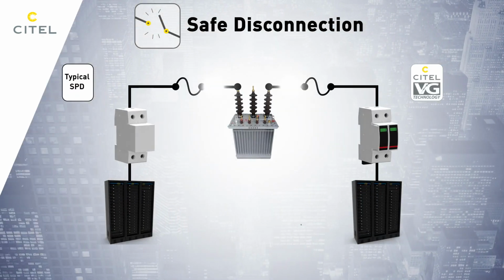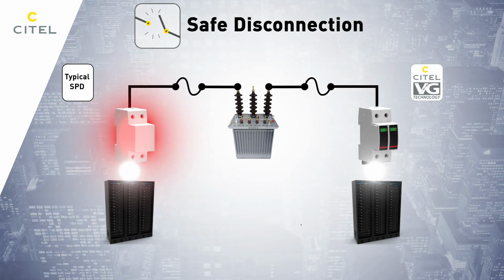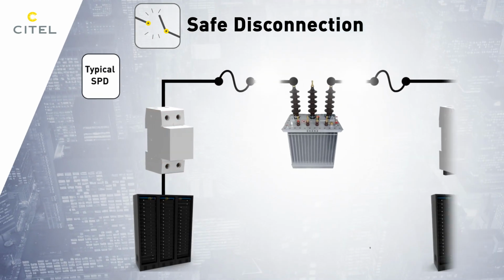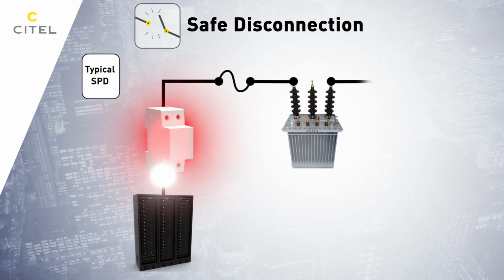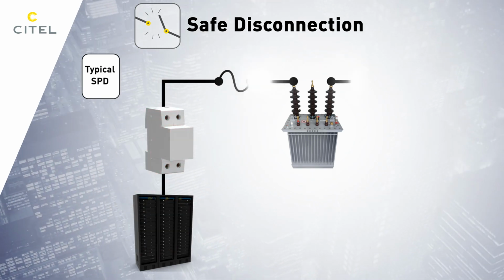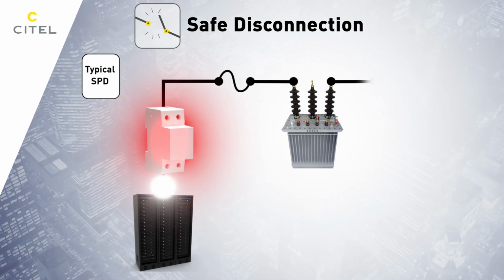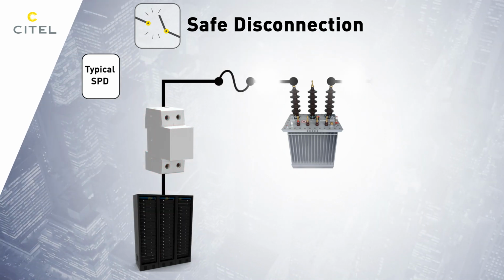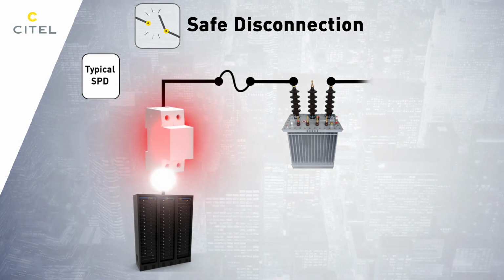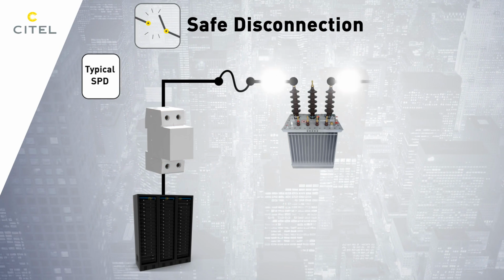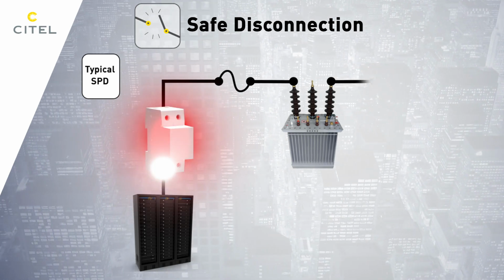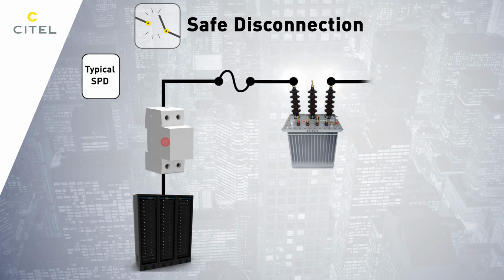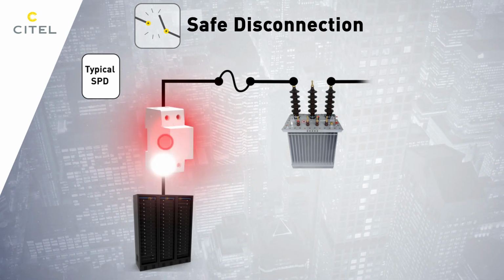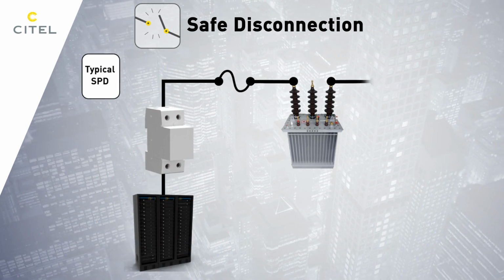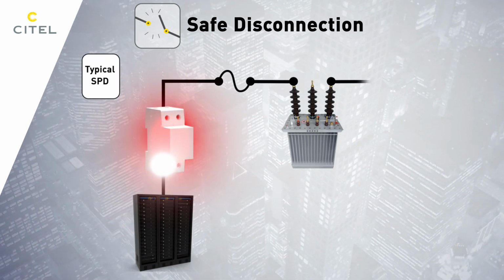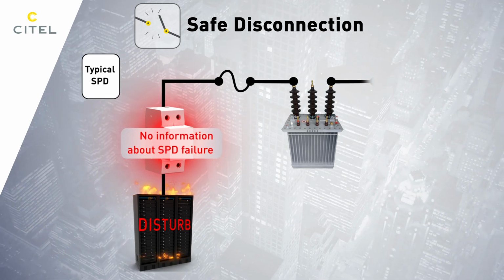A surge protection device must safely disconnect from the electrical network. This is especially important for MOV-based SPDs, which can experience degradation over time due to repeated exposure to surge events. As the MOV reaches the end of its service life, its internal resistance decreases. A reduction in internal resistance leads to an increased short-circuit current flowing through the SPD. In such cases, the thermal disconnection function must interrupt the current. If the short-circuit current becomes too high and the thermal disconnection can no longer interrupt it, an arc may form, which could lead to a fire.